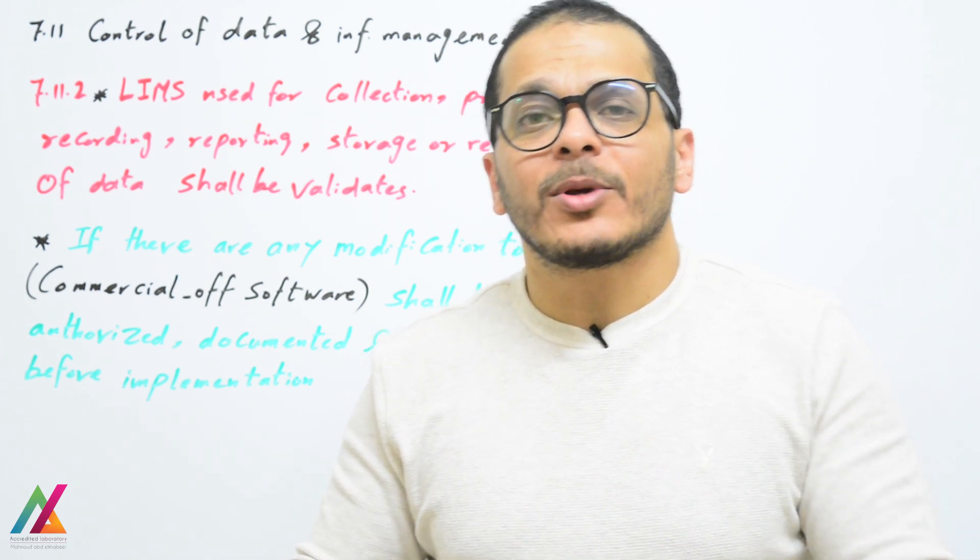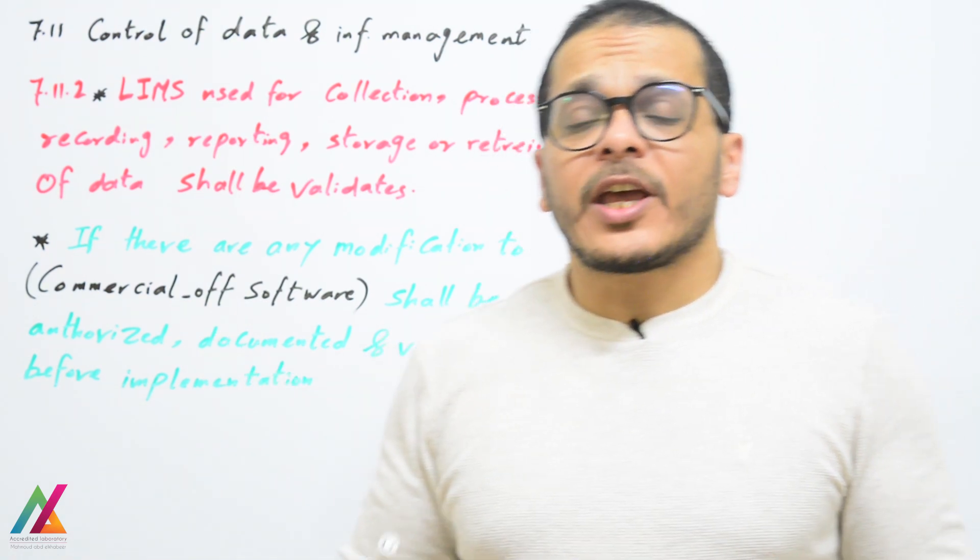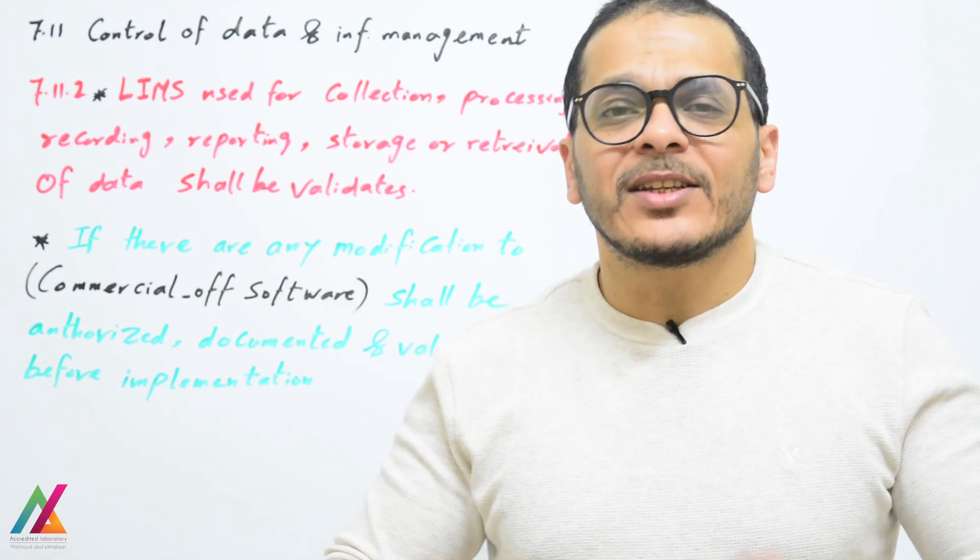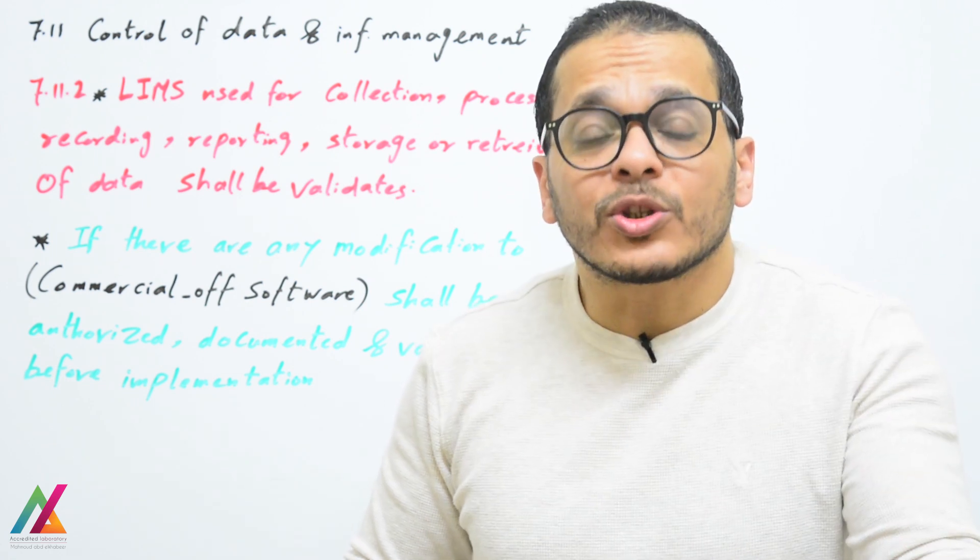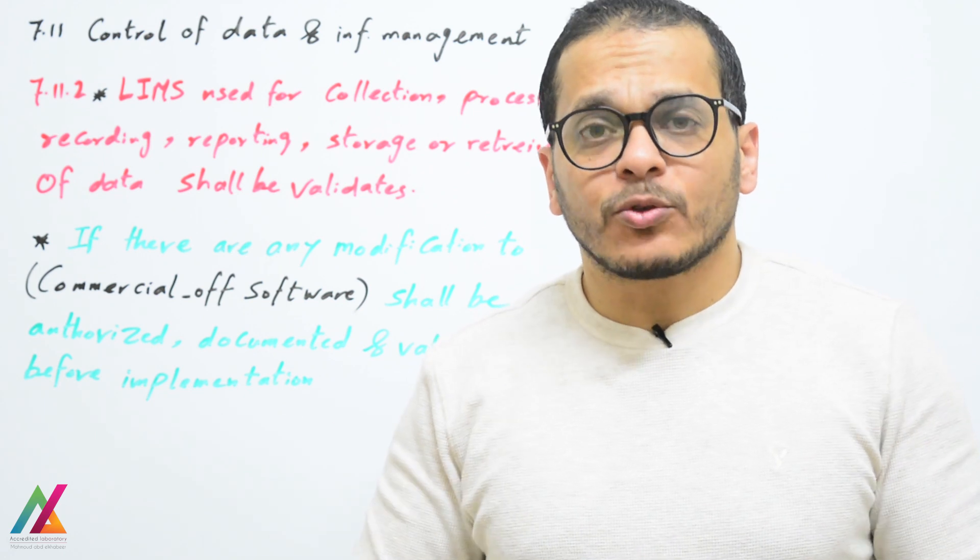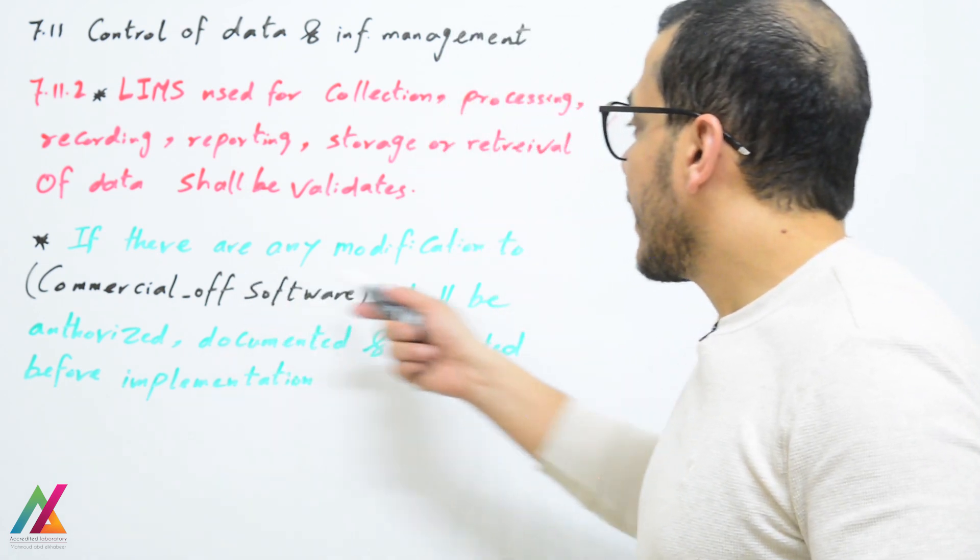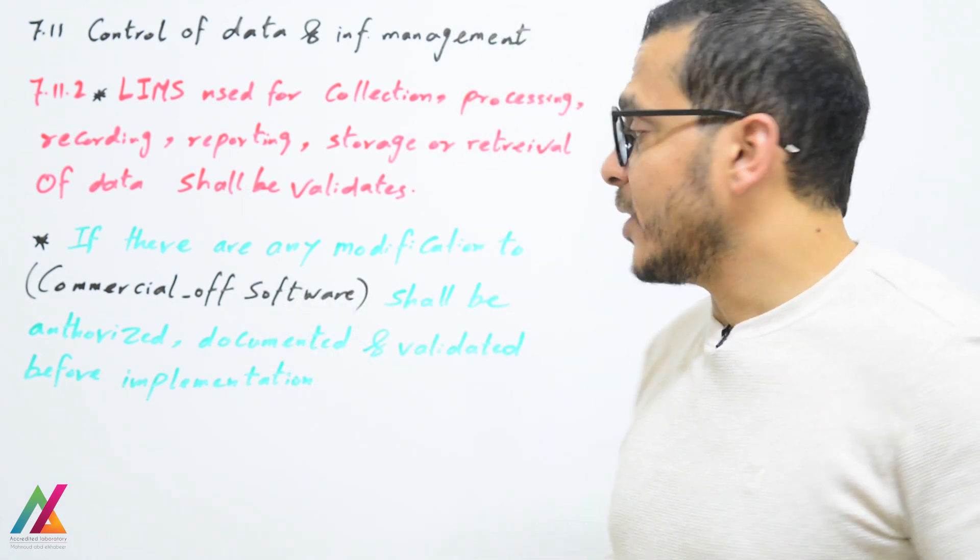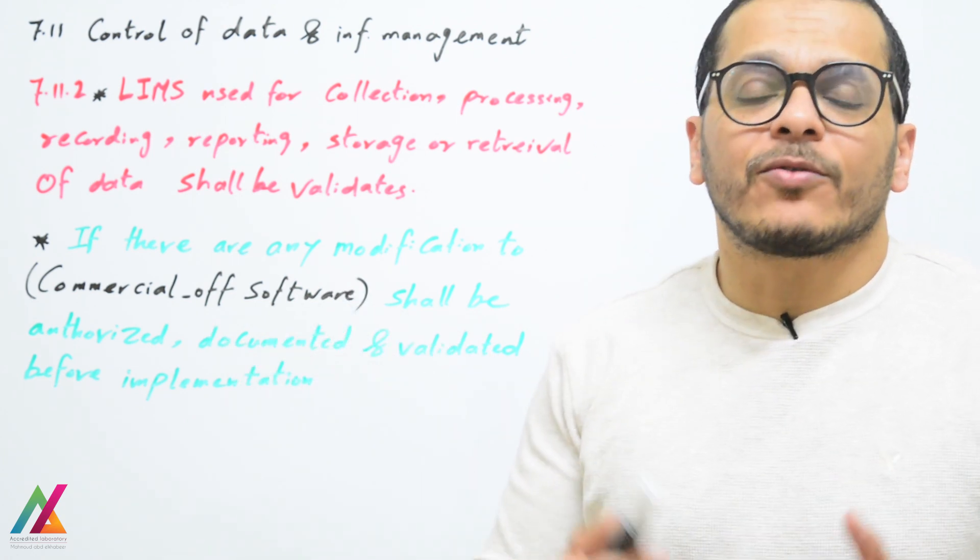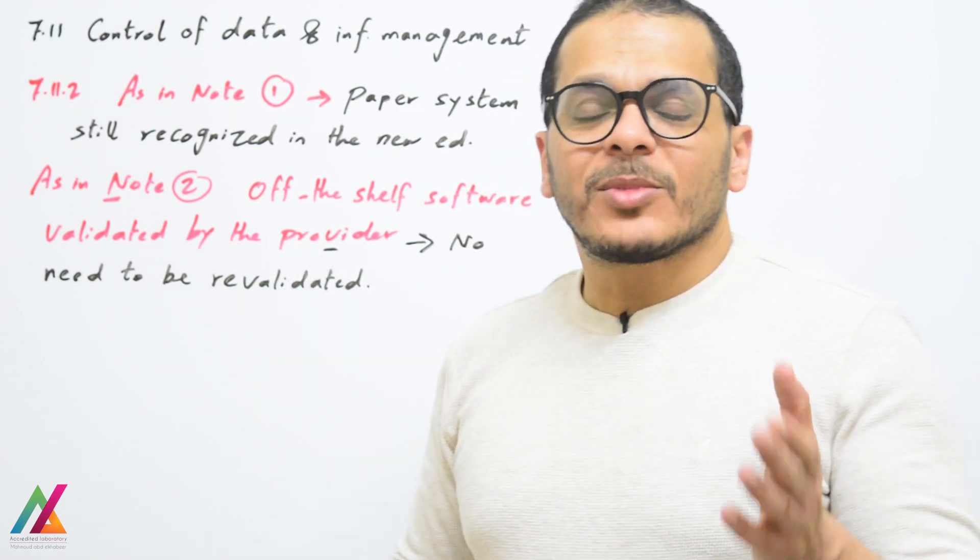If there are any modifications to commercial off-the-shelf software, which is ready-made software such as software for instruments or such as LIMS, this ready-made software shall be validated before implementation by the provider. Any modification from the provider to these softwares shall be authorized, documented, and validated before implementation.